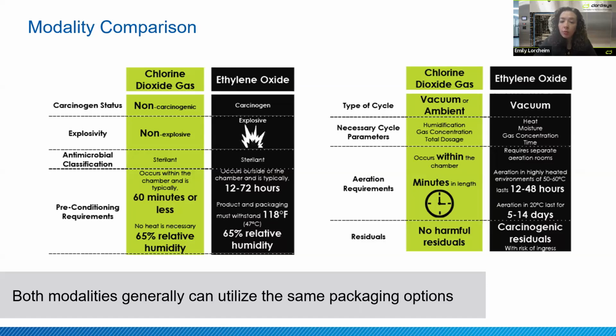Also, you can have an ambient or vacuum pressure sterilization process with chlorine dioxide. This gives a little bit more flexibility, especially if you have things like a plunger in a pre-filled syringe, or if you have packaging considerations where excessive vacuum would be harsh on it. Now, the necessary cycle parameters for chlorine dioxide are humidification, gas concentration, and dosage. It's a little bit different with ethylene oxide, mainly being the heat component to it. So ethylene oxide needs to raise the temperature of the process in order to get better efficacy. Also, time is more of the controlled measure rather than dosage. We can have a varying time exposure, but as long as we maintain that dosage, we see consistent kill.